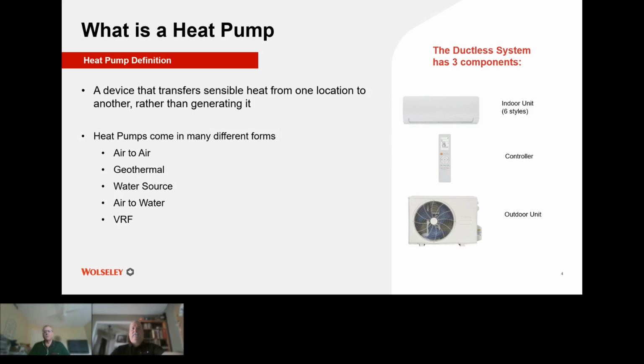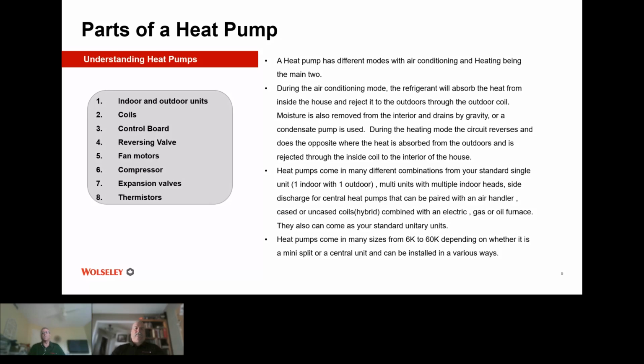So, parts of a heat pump. The heat pump has different modes, with air conditioning and heating being the main two. During the air conditioning mode, the refrigerant will absorb the heat from inside the house and reject it to the outdoors through the outdoor coil. Moisture is also removed from the interior and drains by gravity, or a condensate pump is used. During the heating mode, the circuit reverses and does the opposite, where the heat is transferred from the outdoors and rejected to the inside coil to the interior of the house.